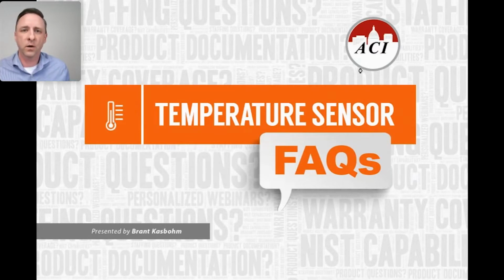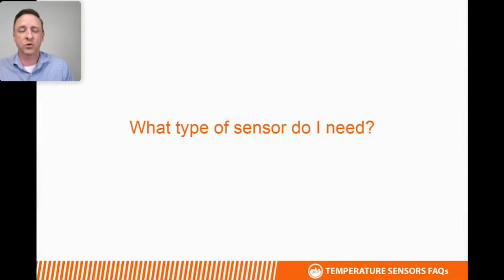So we're going to start by talking about a few general questions regarding temperature sensors or temperature sensing in general. And then we'll move into some specific configuration questions for duct and room and outside air and the like. So over the years, the most common question is, what do I need? Which type or which sensor do I need? And I think that comes from people looking at our data sheets and seeing dozens and dozens of options. And so when looking at which specific configuration you need, whether it's a duct mount, immersion, averaging, and the various lengths and options, the job requirements are going to determine that, whether you need a waterproof or weather-tight box or which probe length you need.